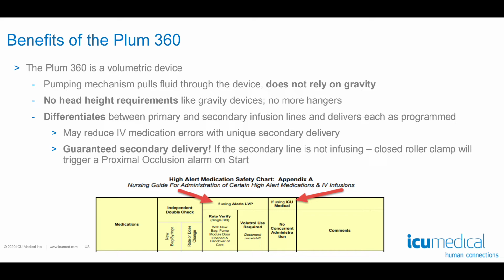First, let's talk about the ICU Medical Plum 360 infusion pumps. This pump is a volumetric device, meaning it pulls fluid through the device and does not rely on gravity. This means that there are no head height requirements like gravity devices, and no more hangers, and most importantly, no more Volutrols or rate verify when using this pump. The high alert medication chart and policies have been updated to reflect this change in practice.